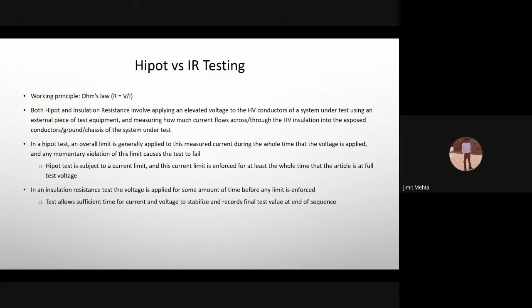Insulation resistance testing, on the other hand, is for components where the current is expected to be absorbed initially before it stops leaking. The final value of the test is what's collected to decide whether the unit passes or fails. So both are essentially insulation testing, just applied slightly differently.